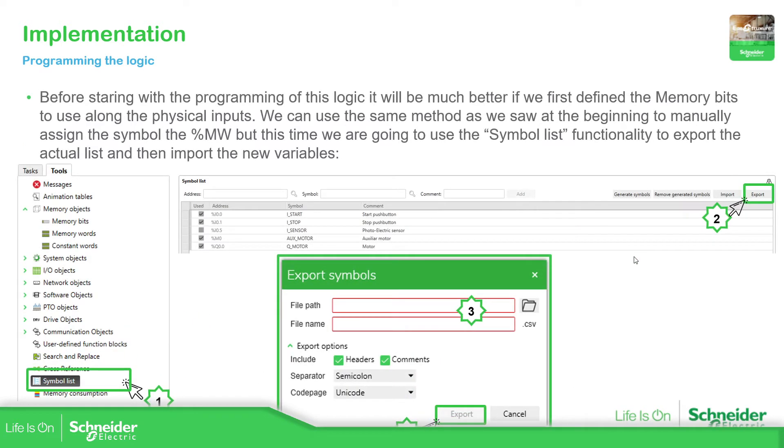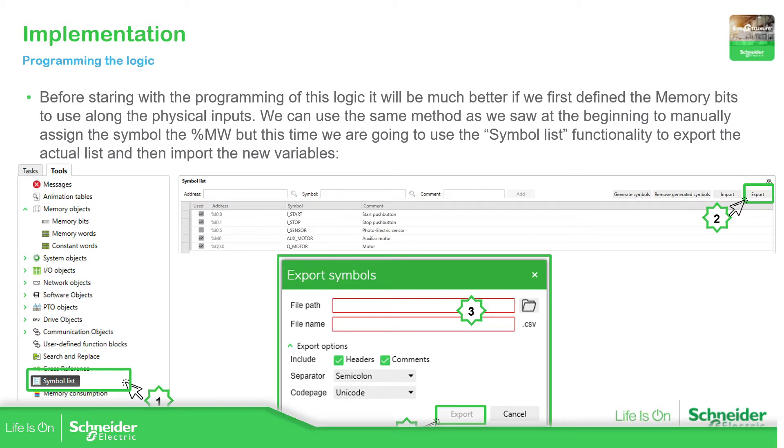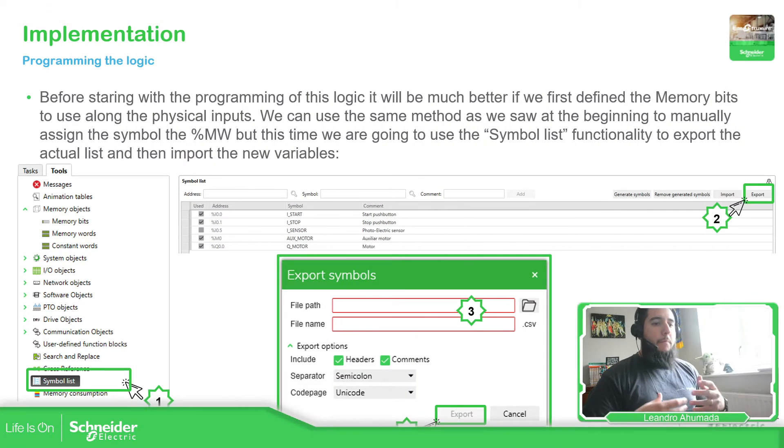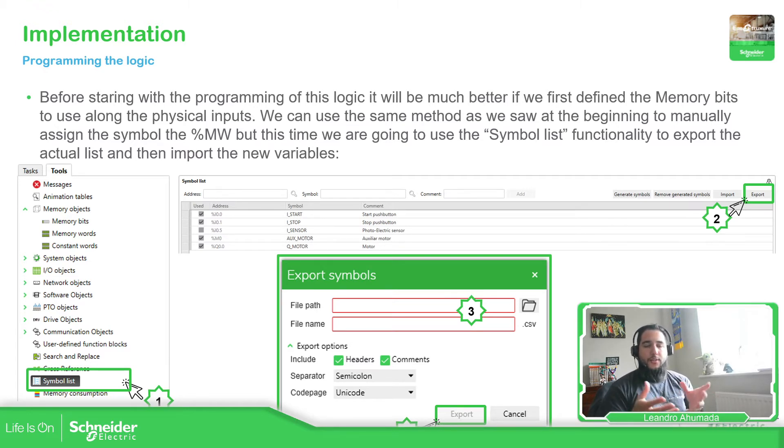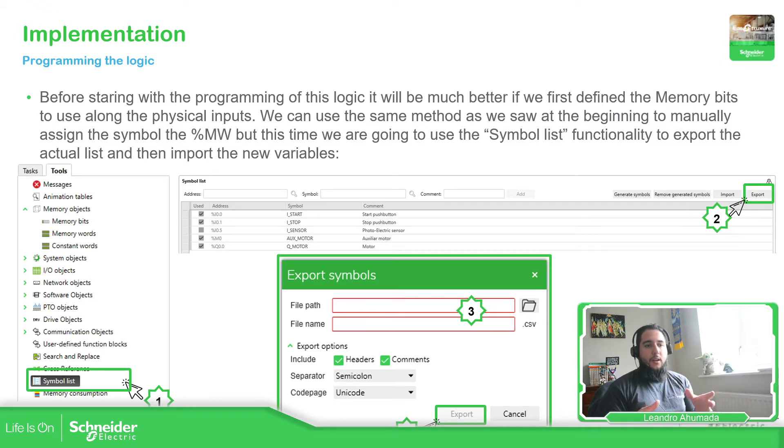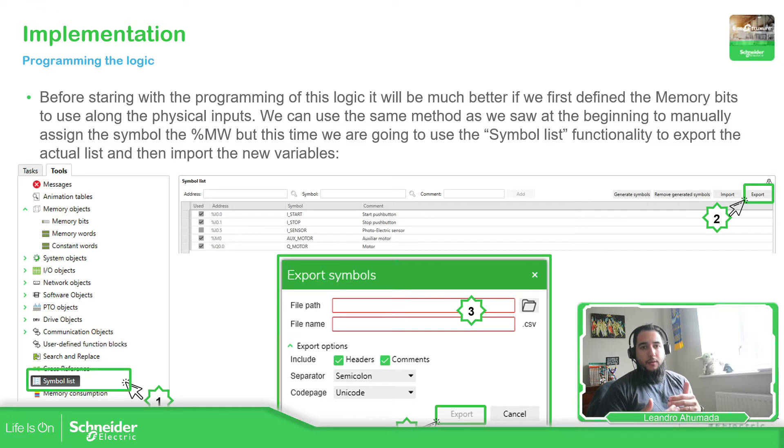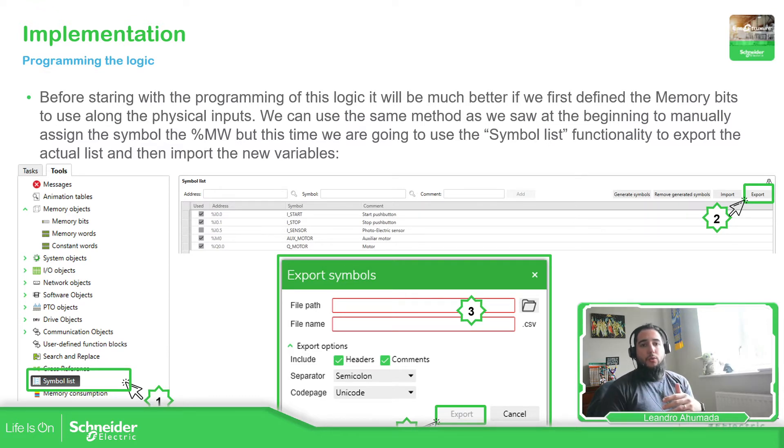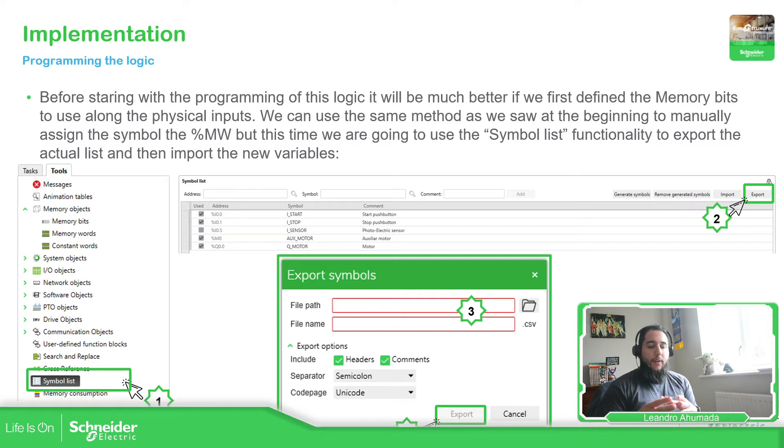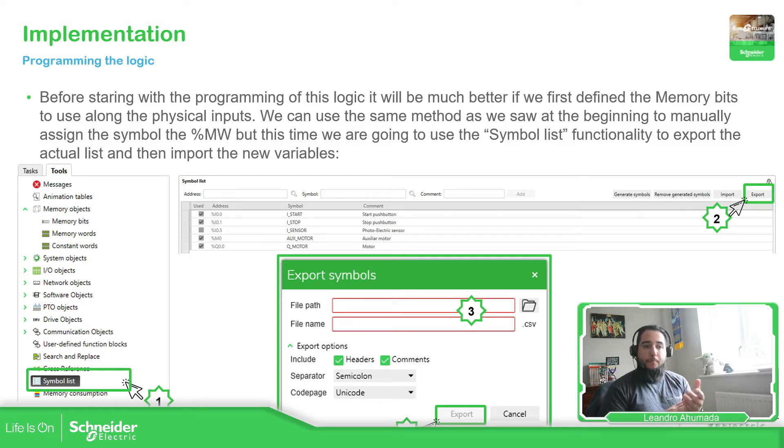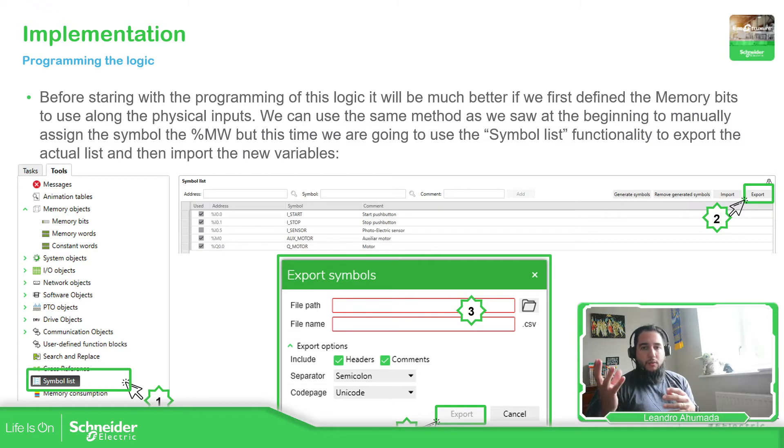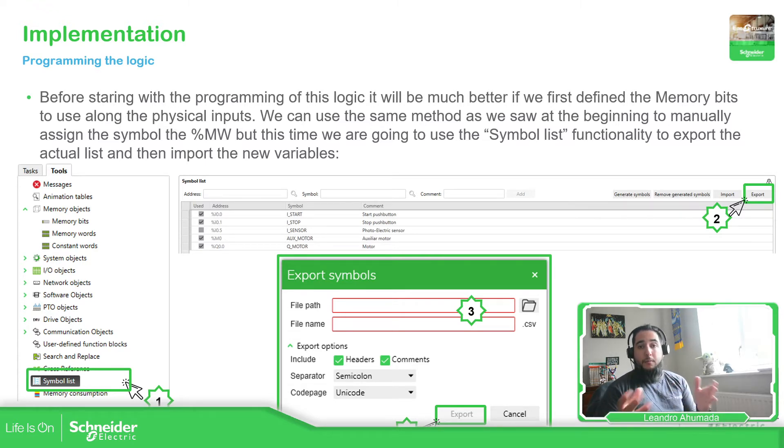And then we have the possibility to export our symbol list into a file and we can edit that file to add more variables. Probably in this small project it doesn't apply, but if you have a huge project, instead of manually adding all the variables in the software, probably it's much better to use an Excel file so you can edit and assign all the variables, the symbol and the position, the memory address, and then you just import that file into the software and it's going to be much easier.